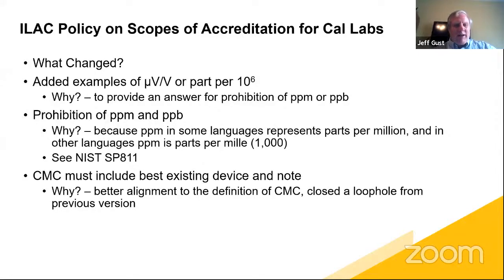And again, why must a CMC include the best existing device? And note, because it's better aligned to the actual definition of the CMC, and it closes the loophole from the previous version. We've still had a lot of laboratories out there whose CMC only covered the uncertainty components of their reference standards, and they never included a contributor of the device that they were calibrating. And they were kind of getting away with this.